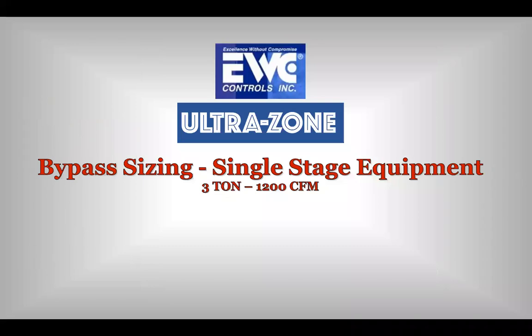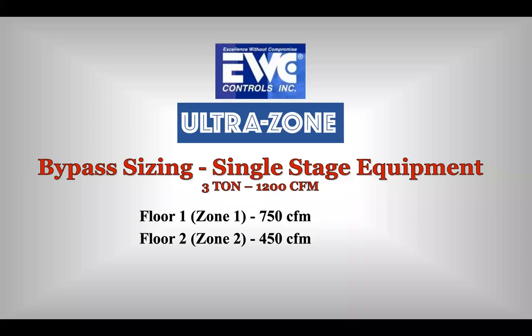So first floor, we're looking at a 3-ton system here, 1200 CFM, single stage equipment. Let's go straight forward, single stage equipment, and see what we're looking at. Floor 1 was 750 CFM. Floor 2, 450 CFM.